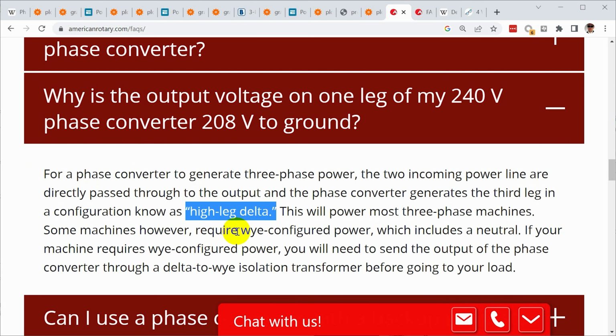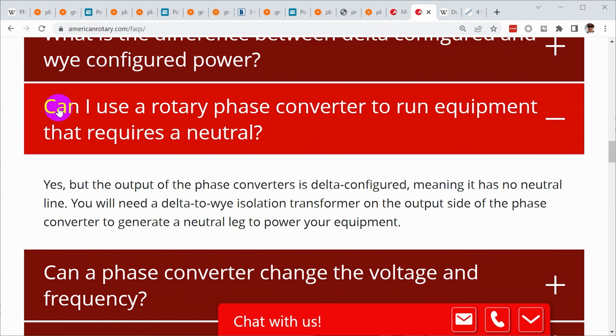Some machines, however, require Y configured power, which includes a neutral. If your machine requires this, then you will need to run it through a delta to Y isolation transformer. There's another question further down asking, can I use it to run equipment that requires a neutral? And the answer is yes, but it's delta configured, meaning it has no neutral. You will need a delta to Y isolation transformer.